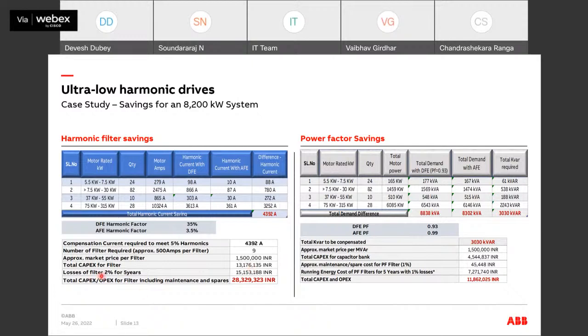Also, there will be filter losses of 2%, and every year it will be multiplied. We have calculated for 5 years, and it comes to around 15 million. So when you add the total capex and opex cost for 5 years for having an additional harmonic filter in the system, this will be approximately 28 million.